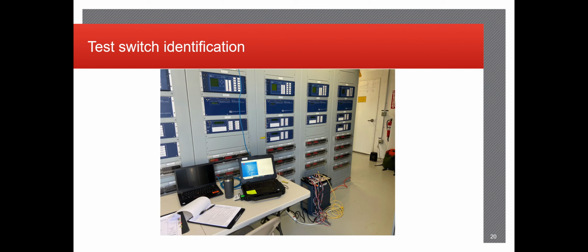Relay testing can be a lot of fun until stuff goes wrong. Yeah, there's instances where you're just cruising along, you're getting good results, everything's lining up as it should, and then all of a sudden something fails and you have no idea why, because you followed the correct standards and testing values that you received from the design engineers. So it can lead to a lot of troubleshooting, a lot of head scratching, head banging sometimes, but all in all, it's a pretty good gig, especially when it's -4 degrees outside and you're in the control house that's heated and everyone else is outside freezing.